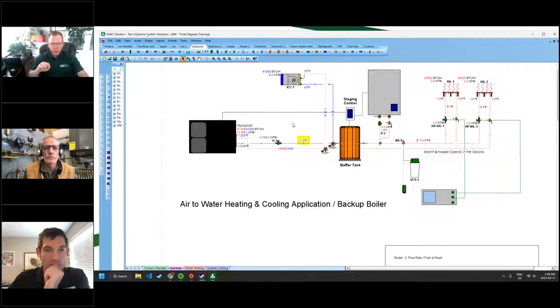So what's happening is we've got the air handler coming on before the buffer tank. And the logic behind that is my air handler is not modulating in cooling. It's a static fixed load that I don't have to worry so much about needing that buffer tank. And the other side that's nice about this is, if this is a house where they want warm floors in the bathroom while they have cooling happening, which happens a lot, this is a piping configuration that's very easy to achieve that.